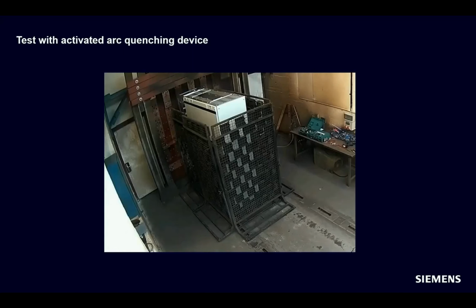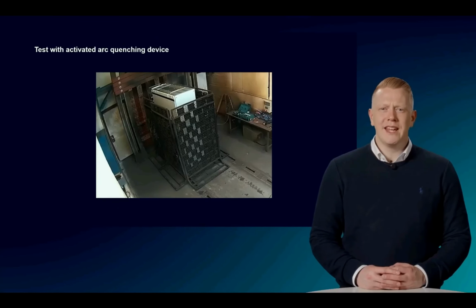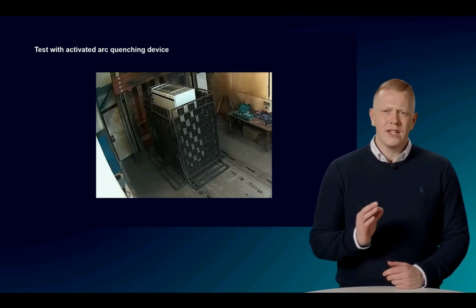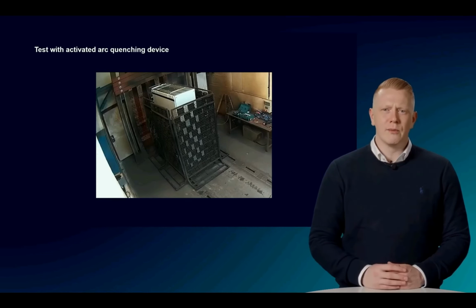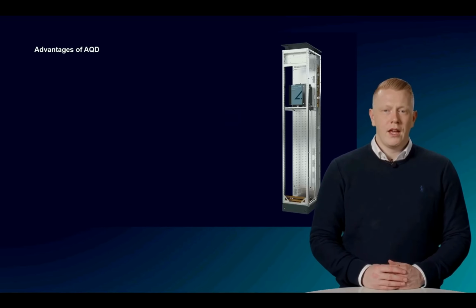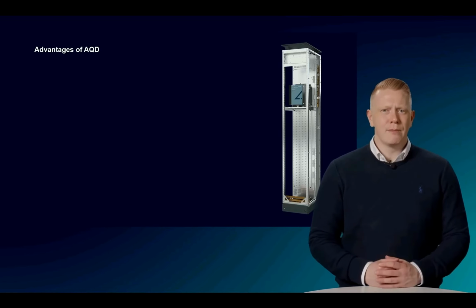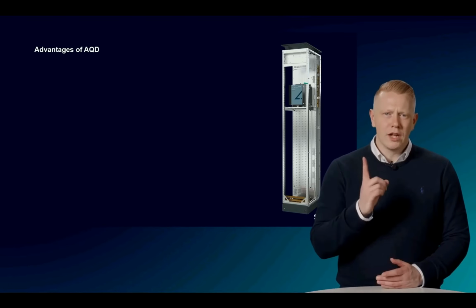In this video, you can see a test with the quenching device activated. The impact on the switchboard is now significantly reduced. And since the quenching device is a purely electromechanical principle, there's another great advantage. After tripping and, of course, eliminating the cause of the malfunction, the system can be easily reset and is ready for use again within a few minutes. This means that no components need to be exchanged or replaced. A simple reset is all it takes to restore the system arc fault protection. In addition, a test function is possible with the system, which can be used up to 100 times.